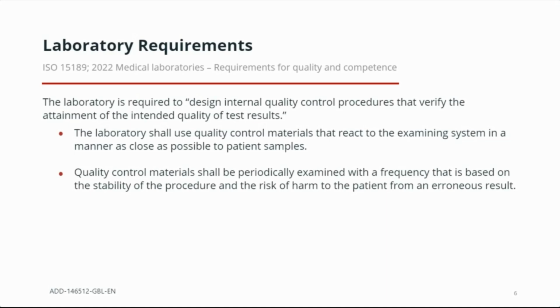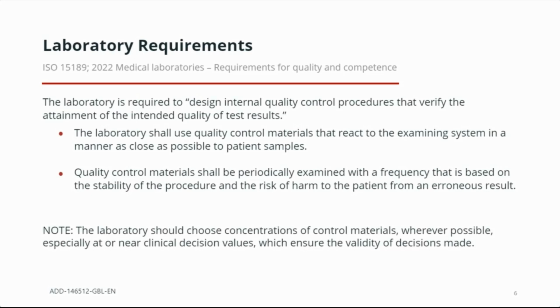So it states, the laboratory is required to design internal QC procedures that verify the attainment of the intended quality of test results. The laboratory shall use QC materials that react to the examining system in a manner as close as possible to patient samples. QC materials shall be periodically examined with a frequency that is based on the stability of the procedure and the risk of harm to the patient from an erroneous result. And there's an important caveat that the laboratory should choose concentration of control materials that are at or near clinical decision values, which ensures the validity of decisions being made.